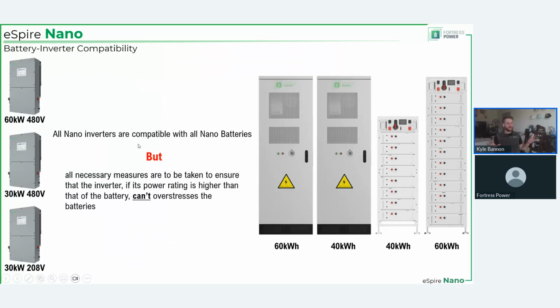So this is again a breakdown of all the different options that you have. You have inverters on the left—30K at 480 or 208 volt, 60K at 480 volt. You can pair any one of those inverters with any one of those batteries on the right. But if, say, you go with a 60 kW 480 with a 40 kilowatt hour cabinet, we are going to limit the output of that inverter to 1C, so you won't be able to use the full capacity of that inverter. But I could see a circumstance where, say, you need 40 kW of 480 volt power—30 kW isn't going to do it. You go with a 60, derate it, ultimately reduce its output, and then pair it with whatever energy storage you choose.